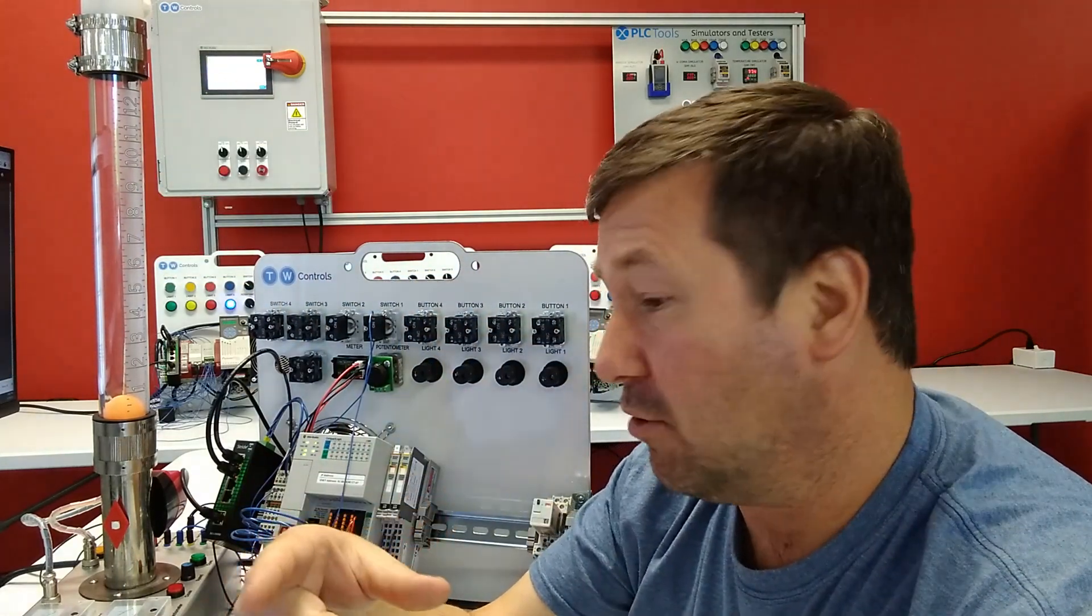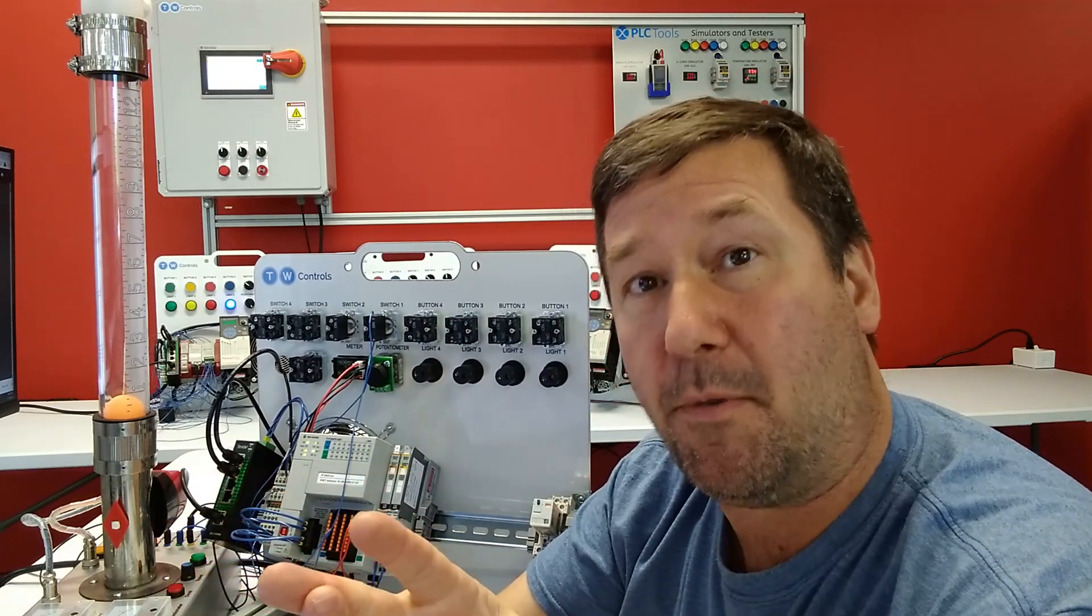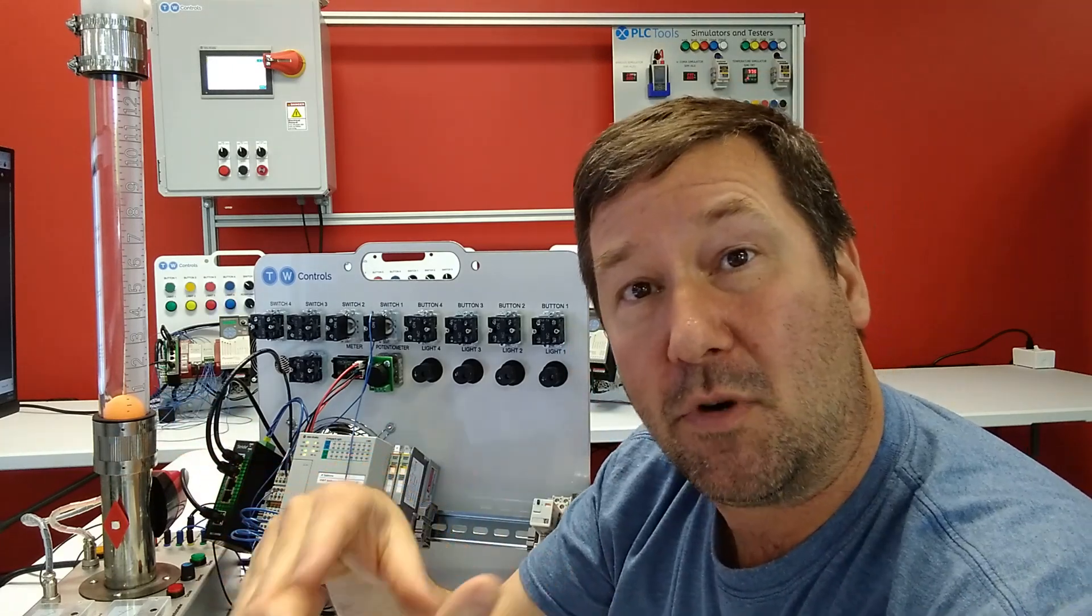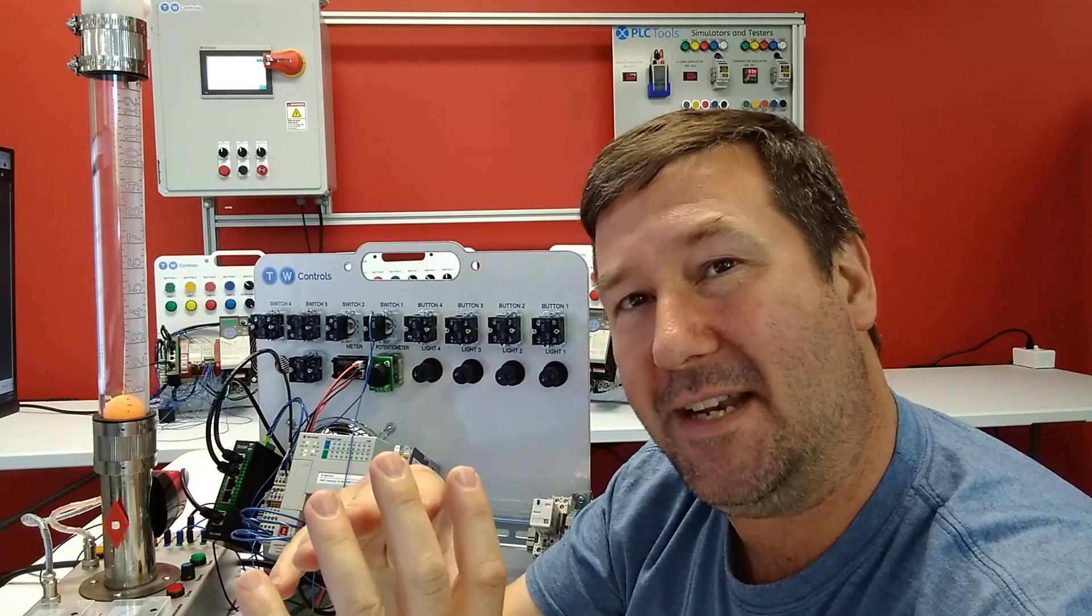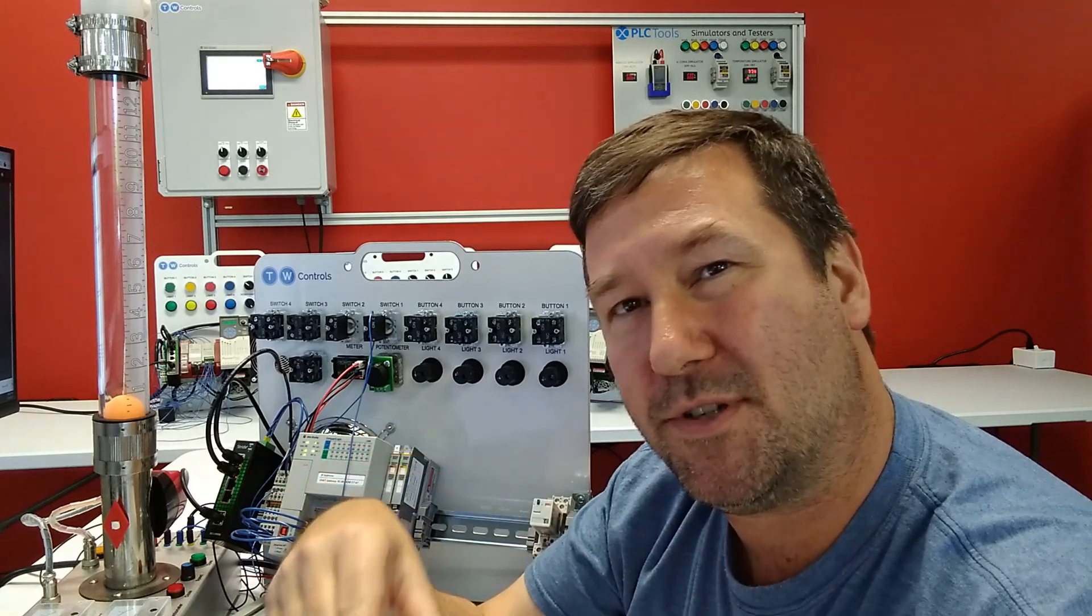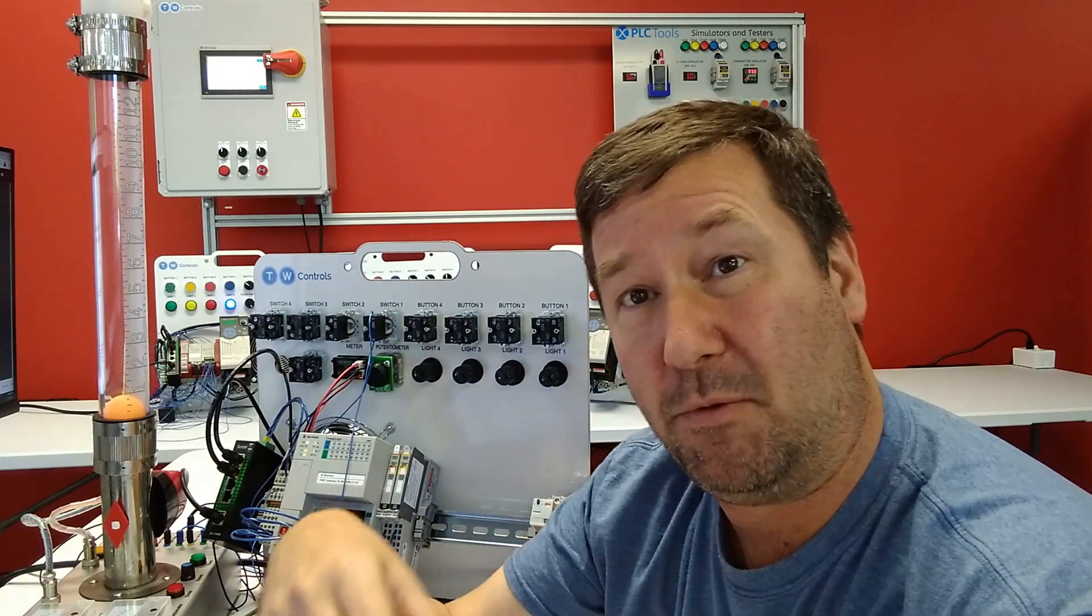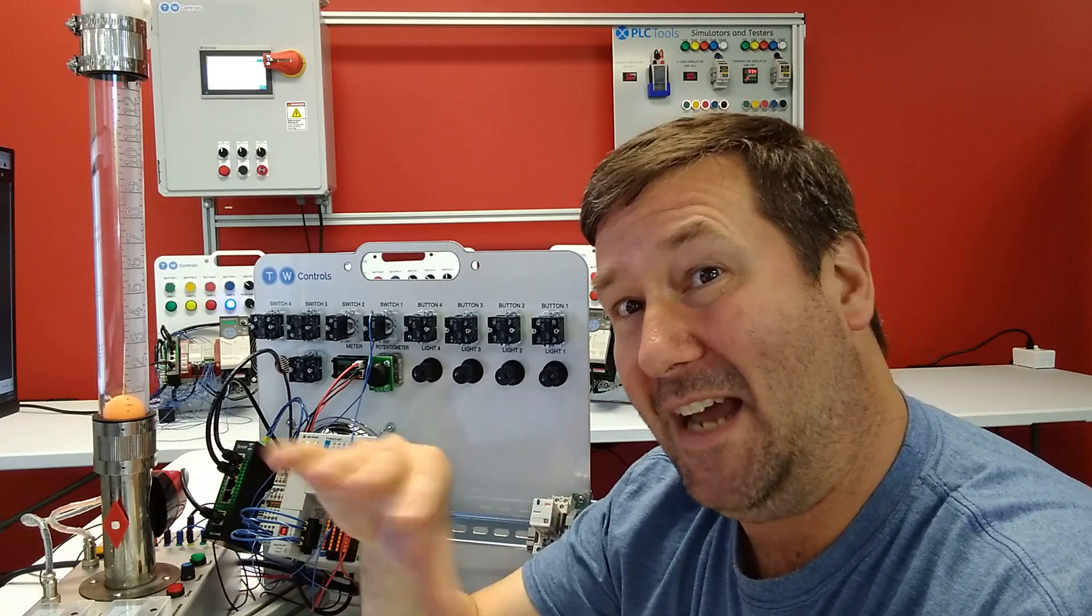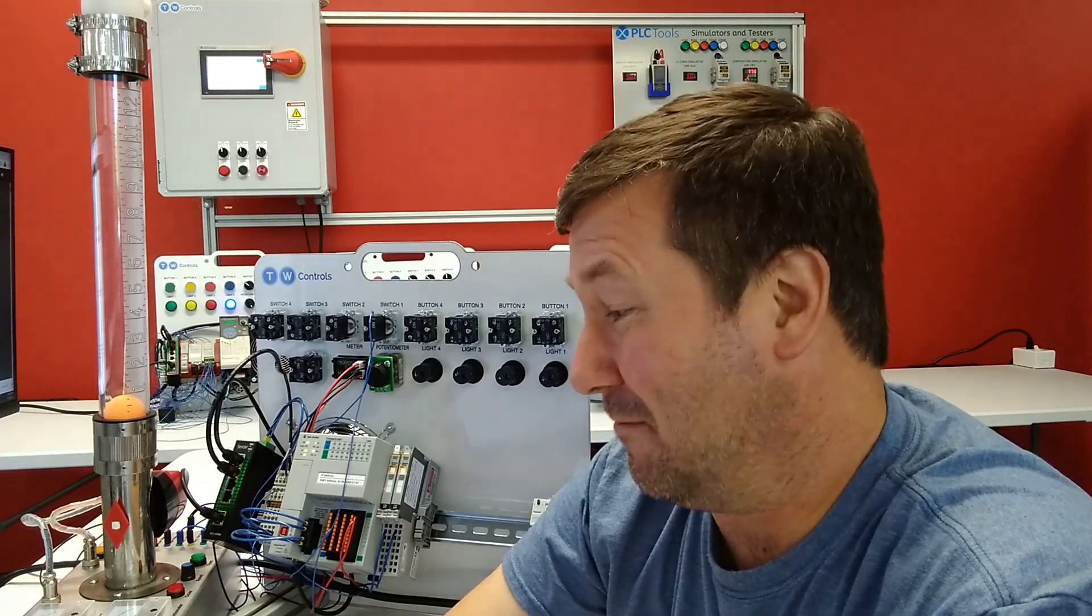In our previous videos we've gone through how to set up your basic PIDE equation, and we've talked about proportional control and integral control. In this video we're going to talk about how they work together. One thing I hear that is not true is people say that the proportional does most of the work and the integral just does a small part. So people will put a PIDE instruction in and won't worry about the I or the D. They'll just put a P value, and then their PIDE doesn't work.